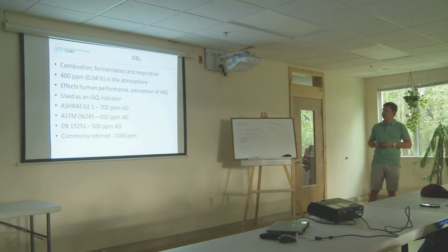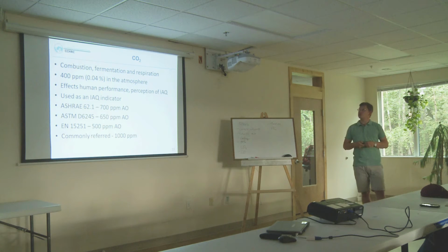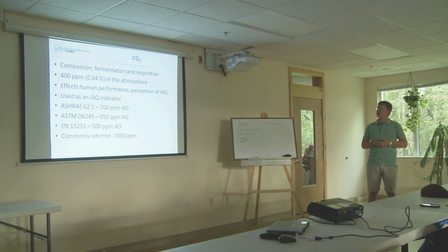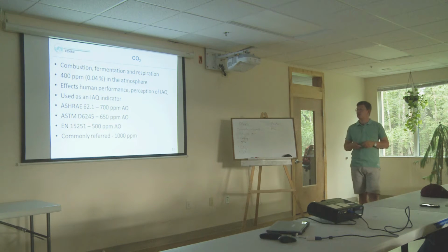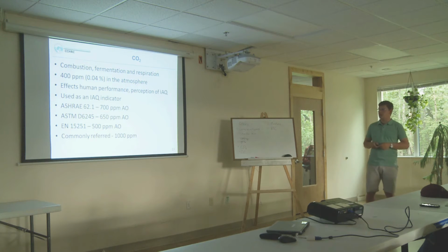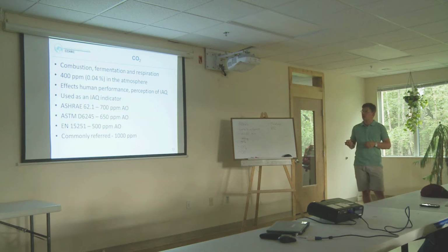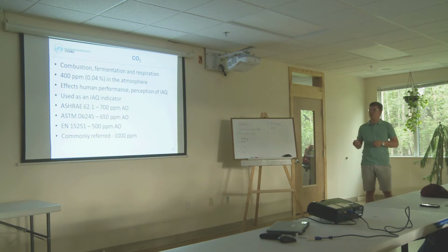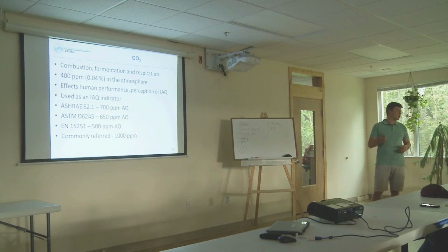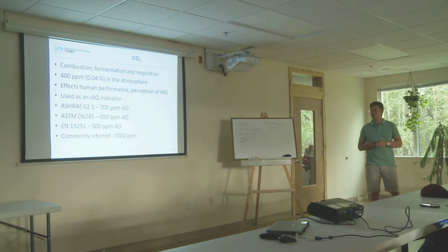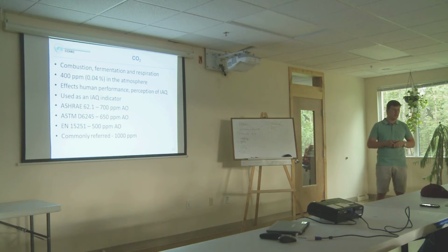And there have been some regulations or recommendations for CO2 concentration inside. ASHRAE here in the US says 700 ppm above outdoor concentration. So if we say that it's about 400 ppm outside, we should have about 1100 ppm inside. The ASTM standard says 650. The European standard says several levels, but the one similar to ASHRAE is 500. And very commonly, we just take 1000 ppm, because give or take 50 ppm, that's not such a big difference. And we say that 1000 ppm is a good level to be maintained inside.